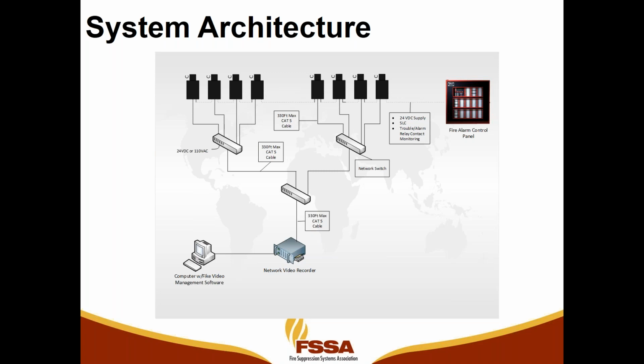The inspection and maintenance, annual and semi-annual, is performed in the software at the computer. Semi-annually, you run an audit report and verify that current conditions match the commissioning. Annually, the report is run again to confirm that the settings are the same as at commissioning. And we force alarms to the detectors so that we can test the communication between the relay on board the camera, the monitor module, and the fire alarm panel.